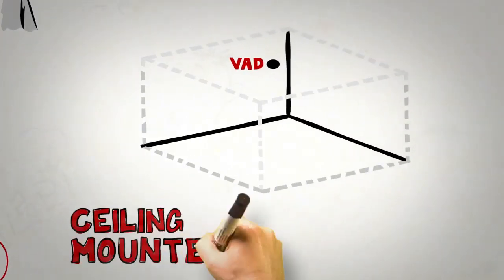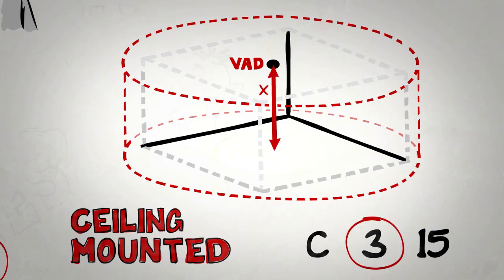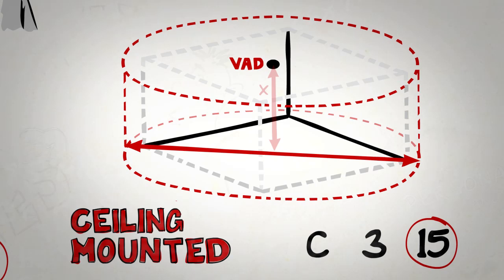The light level for a ceiling-mounted VAD is measured in a cylindrical shape. Here, manufacturers will show you a code like this one, where C stands for ceiling category. 3 is the maximum height at which the device should be mounted, and 15 refers to the diameter of the cylindrical area covered. In this instance, 15 meters.